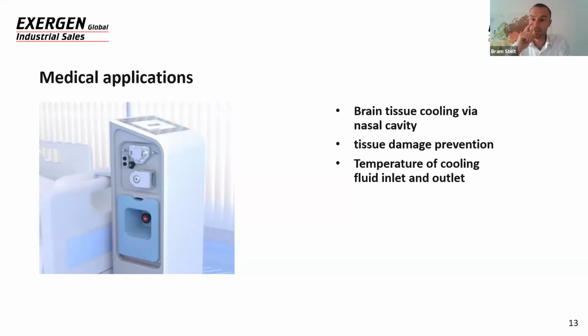Through the nasal cavity, so there's a tube with cooling fluid going in one nostril, and it comes back in from the other, and from the nasal cavity it cools the brain tissue. What you see here are two IR sensors, where again a disposable tubing cartridge can be clicked on in such a way that the two tubes, the inlet and the outlet, the in and the out, can be measured. And by measuring the delta T in combination with the blood flow, they know the cooling capacity of the system, and they can control the cooling of the brain.